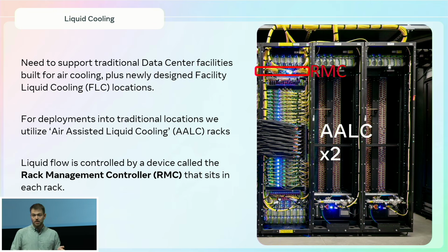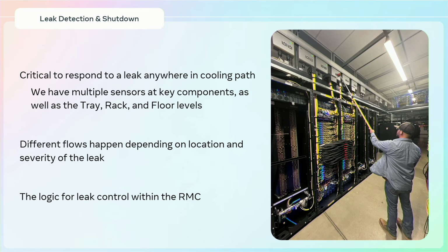To manage liquid, we have the RMC, or Rack Management Controller. It sits within the rack and constantly monitors a number of different components for leaks. It's safely at the top of the rack, to make sure that if there is a leak, it doesn't drip onto it and shut it off. It connects to the AALCs to tell them to shut off, or to what we call the valve train at the facility level, which shuts off the valves from the liquid coming in from the building if there are issues. So why do we need to do this?